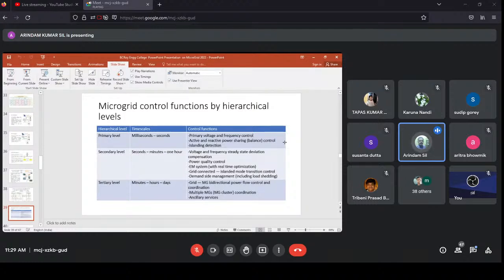This can be done from storage, and islanding detection has to happen immediately when there's a fault, overloading, stability issues, or transience in the microgrid itself. Therefore, it has to be handled on a time scale of milliseconds to seconds, with decision making for islanding detection and further enhancing and controlling the situation. Such control functions work at the primary level.